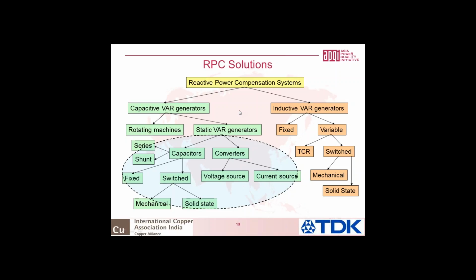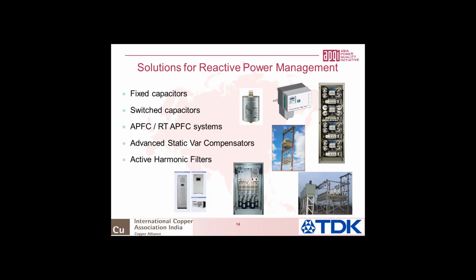And since we are primarily talking about compensating inductive loads, what you see on the next screen are some of the most popular reactive power compensation systems which are used. Of course, fixed capacitors are still very popular, not only in low voltage but also in medium voltage. Then we have mechanically switched capacitors, more often used in medium voltage substations. So depending on the time of the day or depending on the seasonal load, these capacitor banks are manually made on and off. Then we have automatic power factor control systems, which are shunt capacitor banks, which are automatically made on and off, which could be real time or which could be a little slow using mechanical switches. Then we have advanced static kVAr compensators, which could be fixed capacitors plus TCR, it could be TCR plus TSC. And of course, you have the latest trend, which is active harmonic filters.